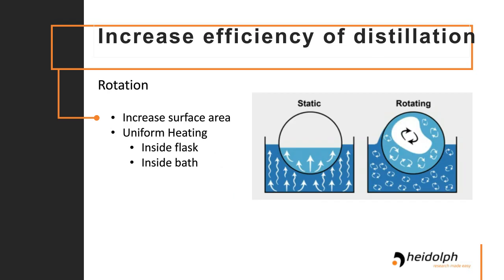The next way to make sure that you're increasing the efficiency of your distillation is the rotation speed. When you've got a static flask, one that's not spinning, you can see that evaporation will only occur at that top level. Along with that, you won't get uniform heating through your medium because it's slowly being heated without any turbulence to really mix it together. When you rotate a flask, you're getting increased surface area because you're coating the entirety of the flask instead of just one layer. Along with that, you're also increasing the speed at which your heating bath uniformly heats the medium inside your flask, leading to much more even distillation and an increased speed of distillation.